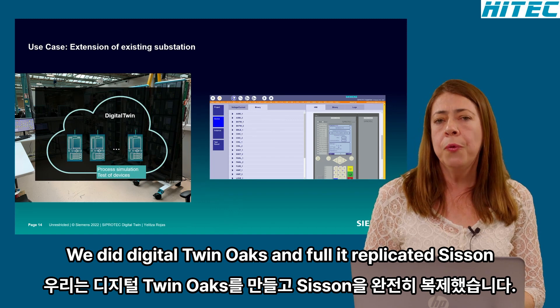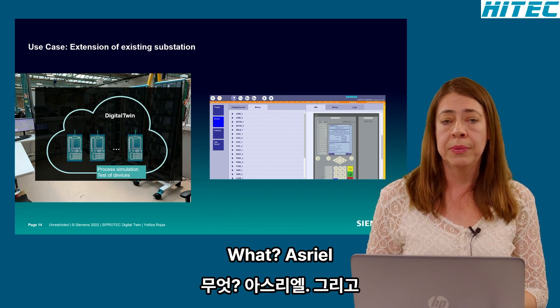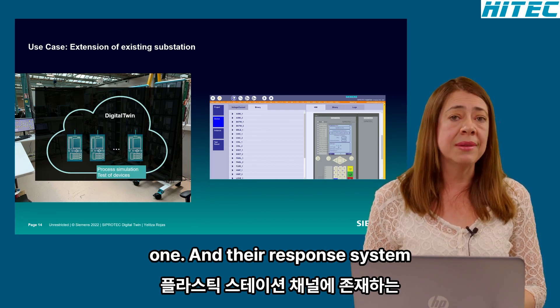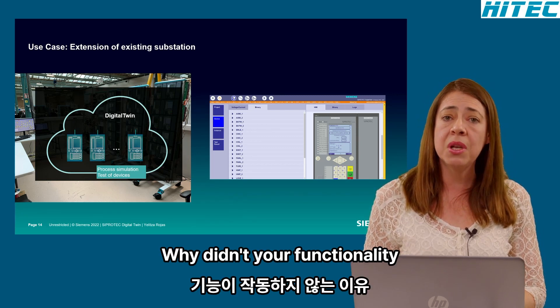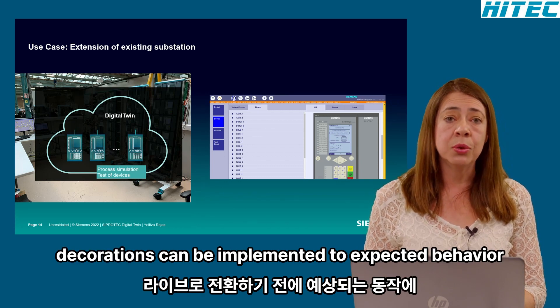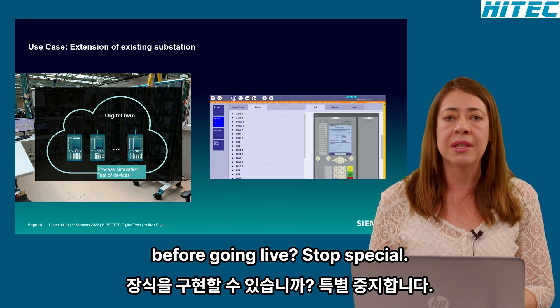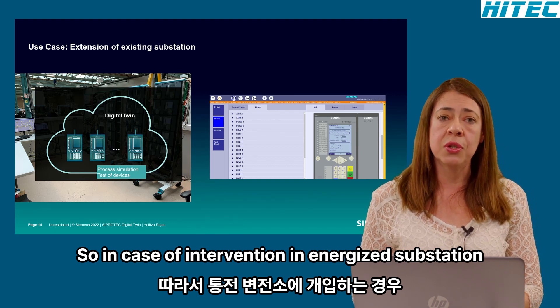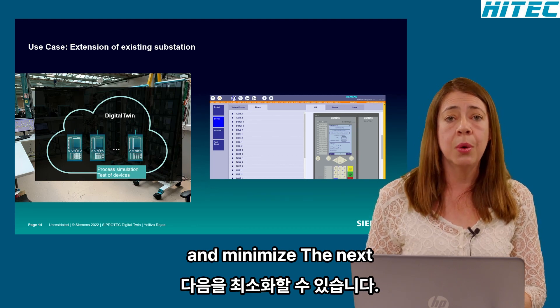With the digital twin, we can fully replicate the existing station and the new bays as well. The system behaves as the real one, and the response of the combined system — existing plus new — can alert on possible failures in communication, wiring, or functionality. Corrections can be implemented to grant the exact expected behavior before going live in the substation, minimizing outages during intervention in the energized substation.